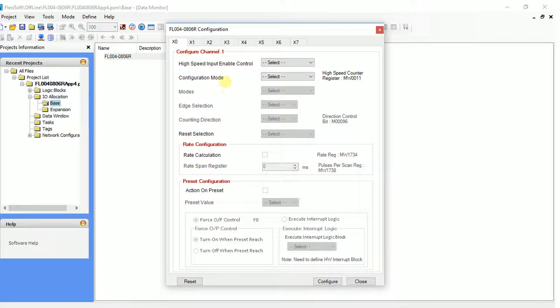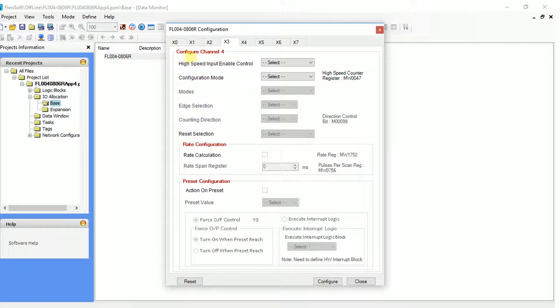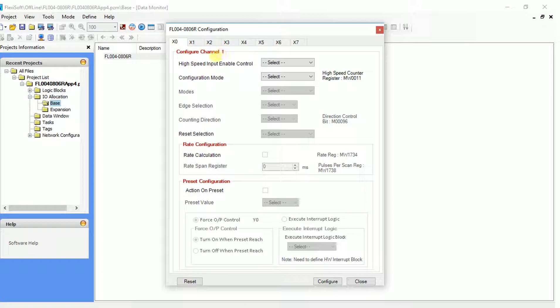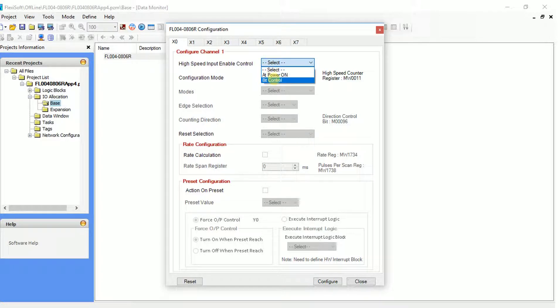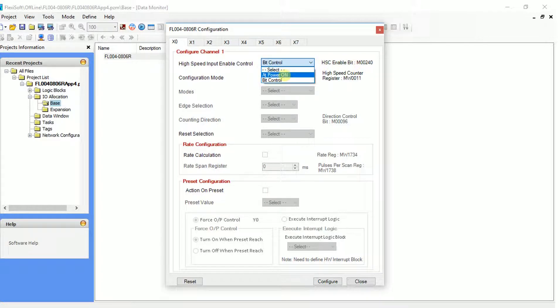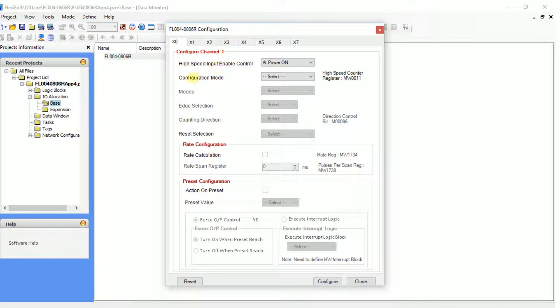Select the input to which the encoder pulses will be read. In the high speed input enable control, if we select bit control, it will enable the input to start counting pulses. If power on is selected, it will start counting pulses immediately when power is turned on.